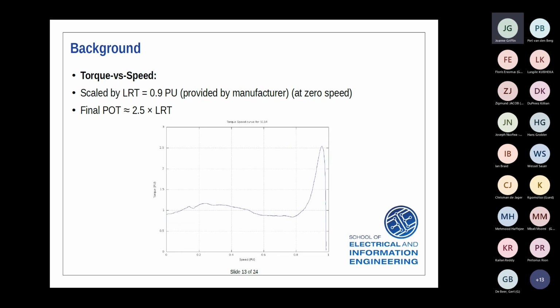You can see this machine's got a single cage rotor with shallow bars, so that's producing the 1 component curve, and you can see there's either the bar, it's not quite on the surface, or there's some resistance in it. You can see the other curve contributing a little bit. And then this feature, we'll talk a little bit later about it. Harmonic torque's very problematic. But on this machine, you can see there's evidence of 1, but it has no effect on the load, which is probably squared or 3x. So it's no impact. Okay.